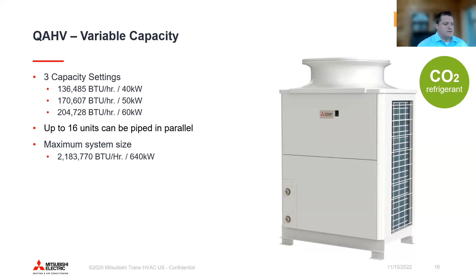And this is kind of what the breakdown of what the unit looks like internally. On the right bottom here, you've got your CO2 compressor, which has some of the same functions and features as our Hyperheat equipment today. And then in the middle, you actually have 6 of these gas coolers. So technically it's not a condensing unit, because it never condenses that refrigerant. We'll talk about that in a couple of the next slides, but basically there are 6 of these gas coolers in series that are in parallel, with CO2 on one side and your cold water in and hot water out on the other side.